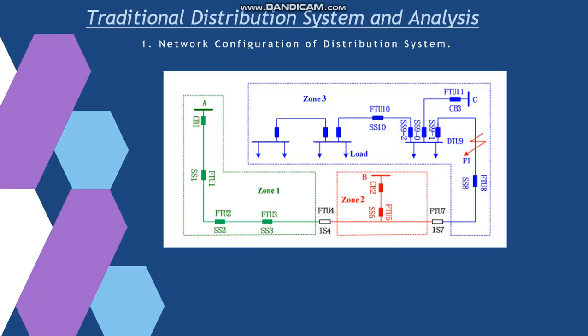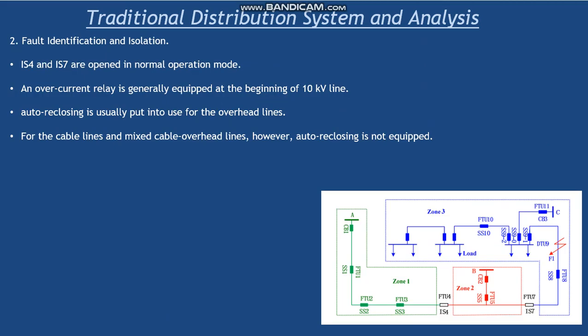This is a traditional distribution system which consists of three zones: Zone 1, Zone 2, and Zone 3. And you can see A, B, C are bus bars of 11 KV. So basically, IS4 and IS 7 are open in normal operation mode. IS4 and IS 7 are basically interconnection switches. Whereas, overcurrent relays are generally equipped at the bus bars, that is at the beginning of 11 KV line, that is A, B and C.